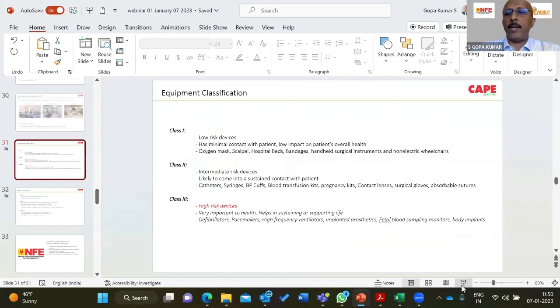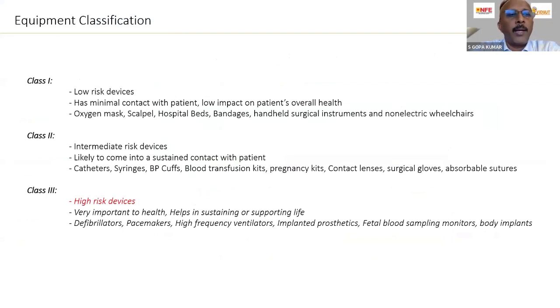So now we go to what we can do or what we have to do. All of you are aware that electrical equipment is classified with respect to safety. Electrical equipment is classified into class 1, class 2, and class 3 equipment. Class 1 is equipment which has a body that can experience a shock voltage if there is an internal fault. In a medical location, we have listed class 1 medical equipment like hospital beds, handheld surgical instruments, non-electric wheelchairs, and so many other class 1 electrical things.